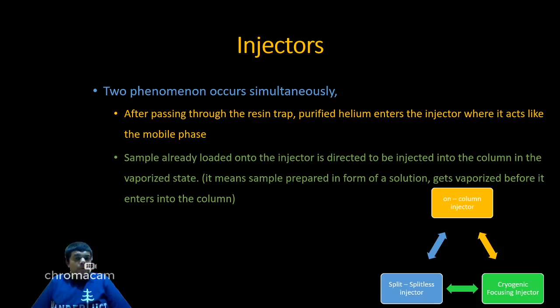Injector mode of operation: split mode and splitless mode. Split mode is an operational method of an injector where a highly concentrated level of analyte is used. When you want to use a high concentration of analyte, you use split mode. Only a fraction of sample is injected, and the rest is vented in the atmosphere. Why? Because when the concentration of sample is too high, and if you enter a large quantity of the sample, the peak might not come in a proper way. So you only require a very little sample. When your injector is operated in split mode, a very little sample goes inside and the rest is thrown away because your sample is highly concentrated.